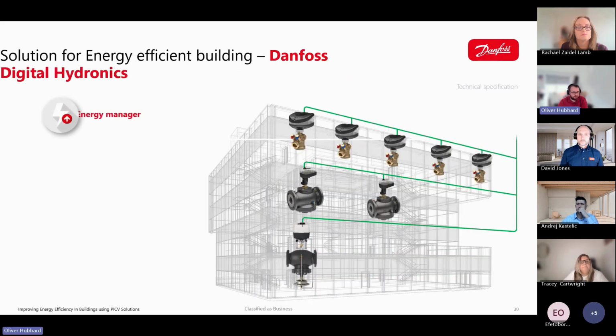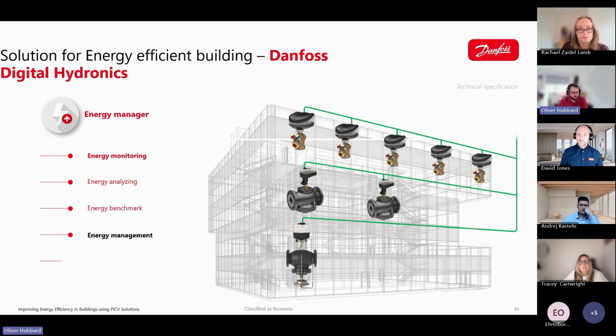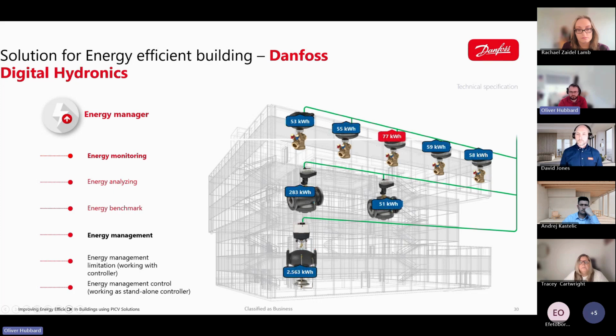So we also have here an example of how this would work within a building, where different valves are receiving different flows due to the demand they need. We can see here that because of the energy monitoring, the ABQM in the middle isn't happy as it's using more than 20% more energy than the others around it, and this means that it may need servicing, or there's another issue that needs identifying.